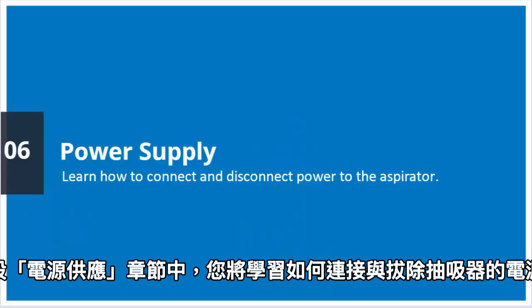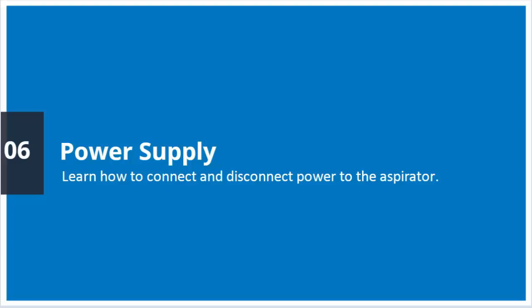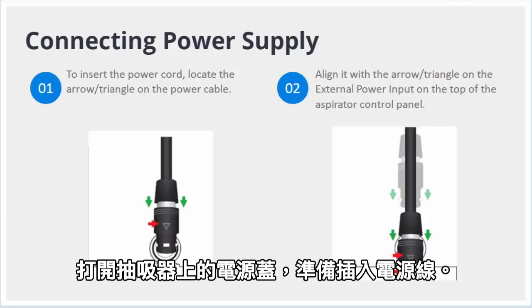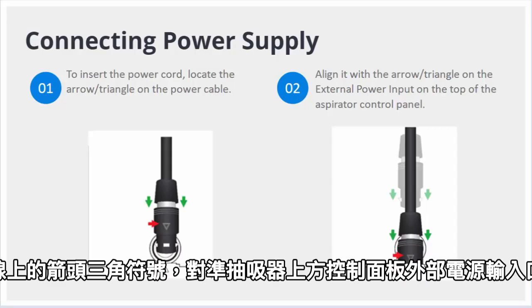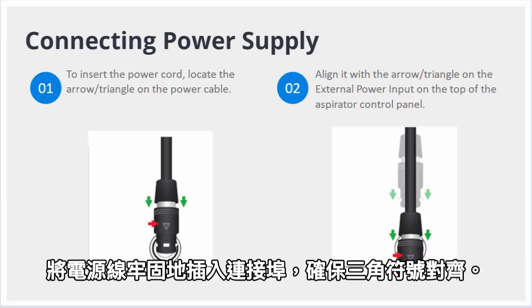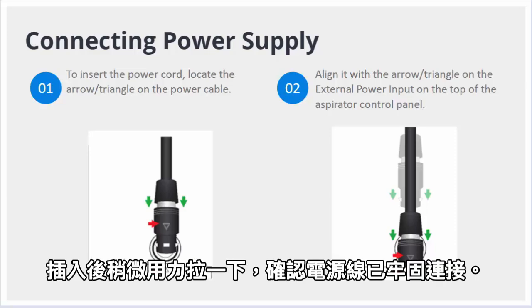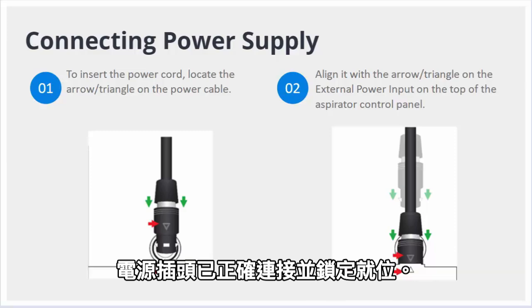In this power supply section, you will learn about connecting and disconnecting power to the aspirator. Open the power supply port cover on the aspirator. To insert the power cord, locate the arrow triangle on the power cable and align it with the arrow triangle on the external power input on the top of the aspirator control panel. Firmly insert the power cable into the connection port with the triangles aligned. Give a firm tug to assure the power supply plug has been connected correctly and is locked into place.